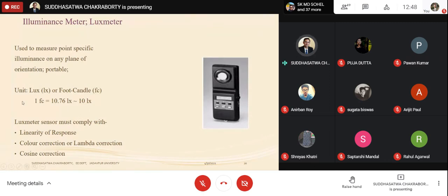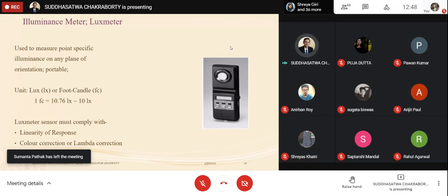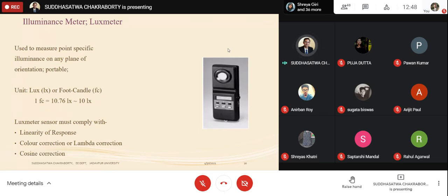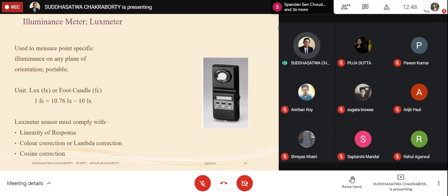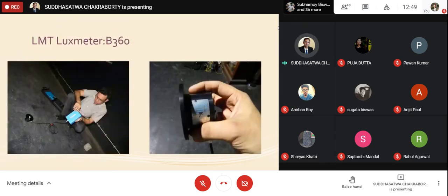When using a lux meter, we need to take care of linearity of response — it should not be very non-linear — and we should apply color correction or V(λ) correction for the human eye. The LMT lux meter I was discussing is the B360, which is a very highly sensitive and standardized lux meter from LMT Germany, costing around 11 lakhs.